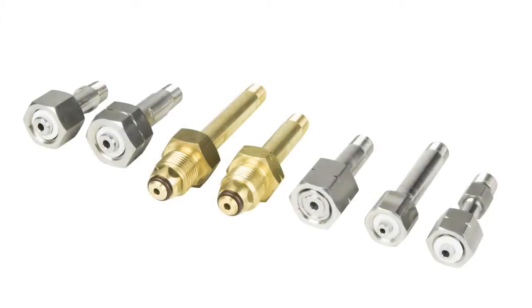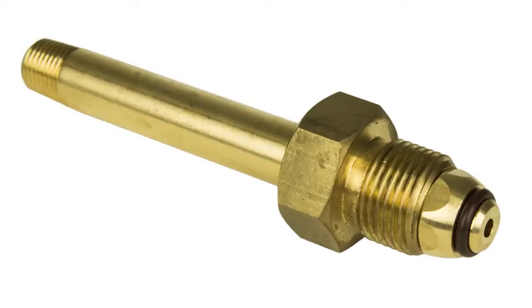The British standard is equivalent to the Australian standard resulting in common valves and connectors. Gas mixtures containing only inert non-flammable gases will typically have a BS3 valve which is equivalent to an AS type 10.